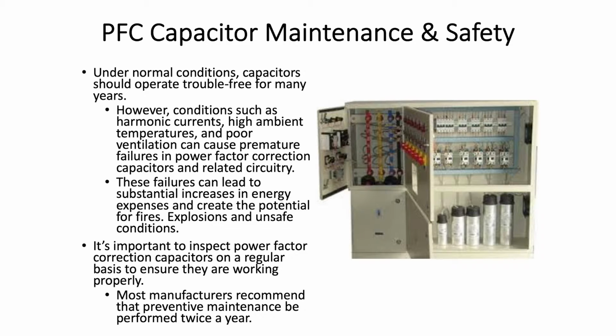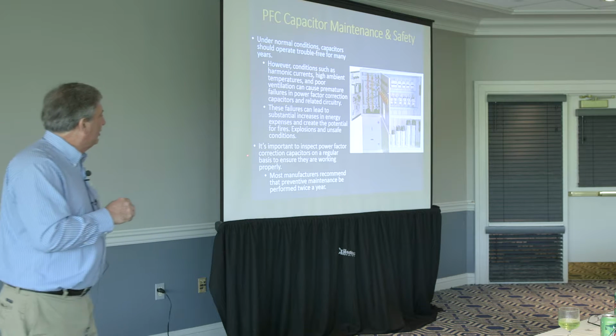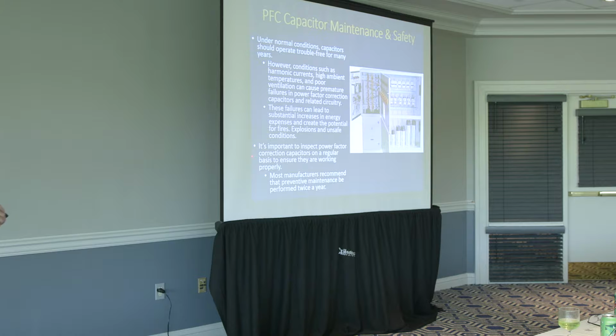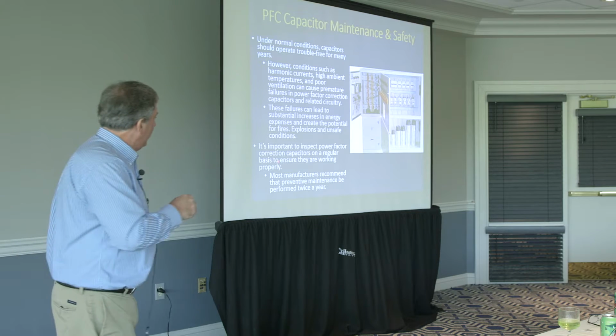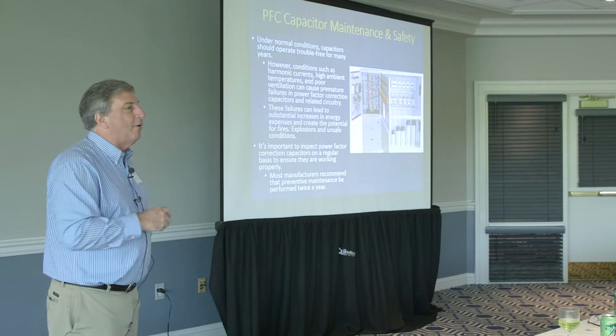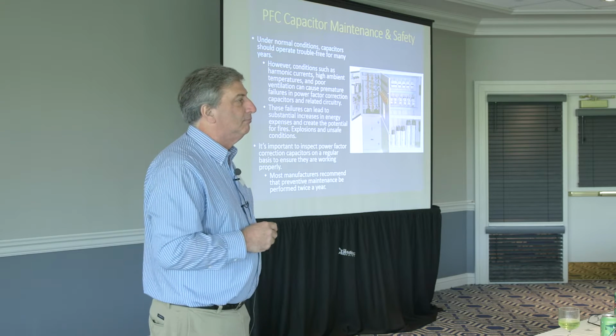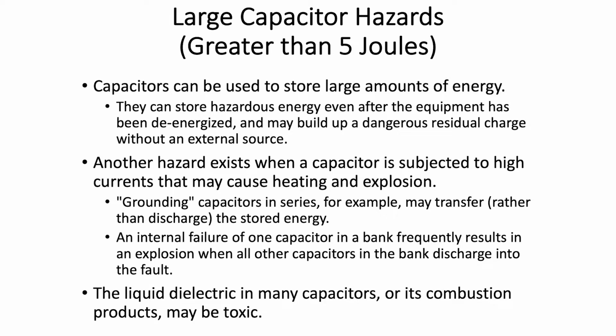Under normal conditions, capacitors should operate trouble-free for many years. Things like harmonic currents, high ambient temperatures, and poor ventilation can cause premature failures in power factor correction capacitors and circuitry. That can lead to substantial increases in energy expense and create the potential for fires or explosions and other unsafe conditions. It's important to inspect power quality or power factor correction on a regular basis to ensure they're working properly. If I look at most manufacturers' literature, it recommends preventative maintenance on power factor correction capacitors twice a year. So every 6 months, you could assume.